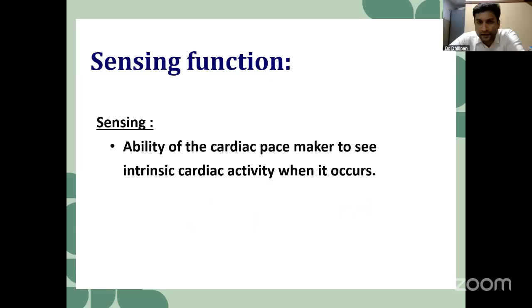Next, we come to the sensing function. The sensing function is the ability of the cardiac pacemaker to sense the intrinsic cardiac activity when it occurs. The sensing function is classified into three categories: one is demand, next is fixed, next is trigger. But when you come to the ER, many recent advanced papers suggest it is better to set the temporary pacemaker in a demand mode. Because with demand and triggered modes, sometimes the patient's cardiac output might differ. When the patient has severe LV dysfunction, you don't know how much the heart is going to pump out, so many people try to keep it in a demand or triggered mode.